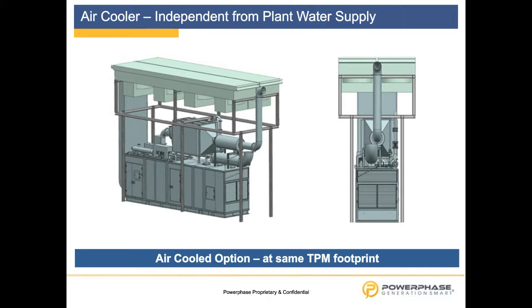I have mentioned the requirement of having water in our box for cooling reasons of the intercooled multi-stage compressor. There are several options. One of them is that we use plant water. The plant water required is in the amount of 200 cubic meters per hour per TPM. We will return that in the exact same amount. We don't consume any. The requirement of this cooling water is around 35 to 40 centigrade, and we will return it 15 centigrade higher than we get it.